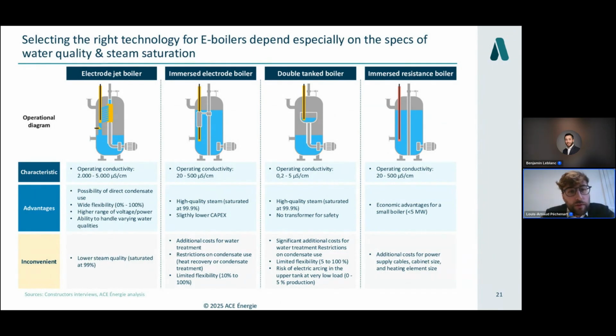If we deep dive a bit into the operational parts, to produce steam here, you will have a water reservoir here in yellow, with little holes. You put water in this reservoir, which makes water jets from the reservoir to the electrode. This will connect both, and electricity will pass from the electrode to the center, the reservoir. As electricity passes through the water, there will be Joule effect, and you will produce heat, so steam. There is also electricity from the electrode to the counter electrode that also produces steam.